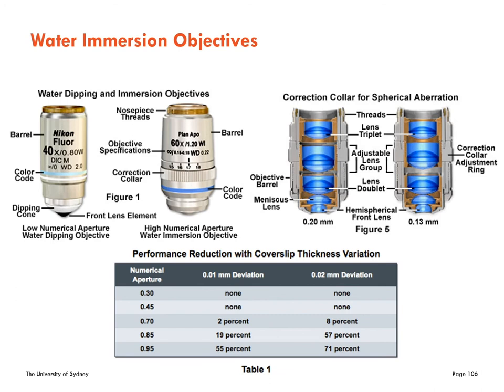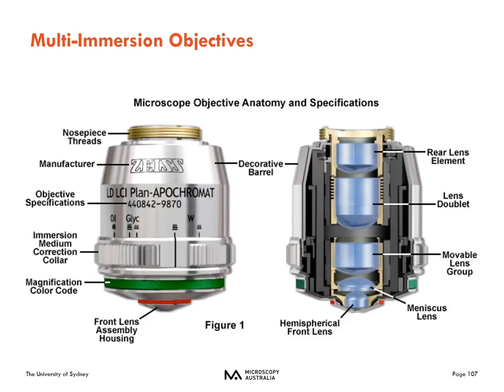You can also use multi-immersion objectives, which are very popular, particularly if you're going from a low mag lens to a higher mag lens. A low mag multi-immersion lens can work with water, glycerol, or oil — you just dial in the immersion fluid you're using, find your sample, and then don't need to clean the sample or lens when you switch to the high mag oil lens. Multi-immersion objectives are very useful.